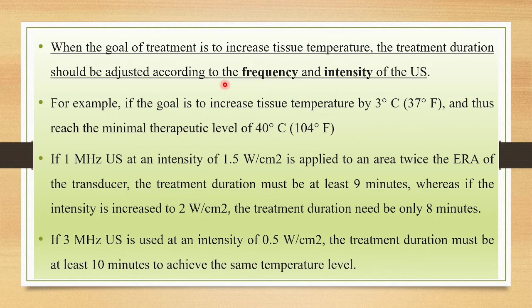And in general, the treatment duration should be increased when lower intensity or lower frequencies of ultrasound are used, when areas larger than twice the effective radiating area of the transducer are treated, or when high tissue temperatures are desired. Normally the treatment duration should be increased depending upon the frequencies as well as the size of the treatment area which you are going to treat.